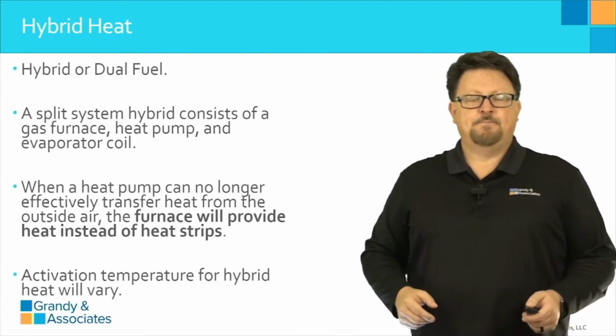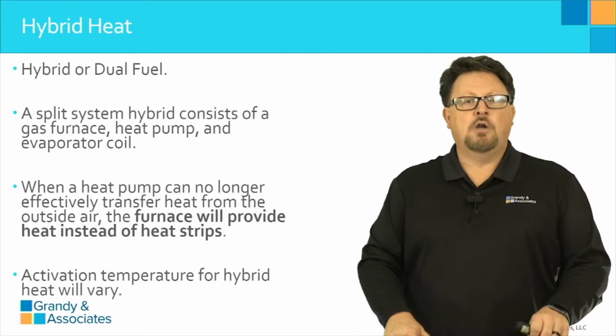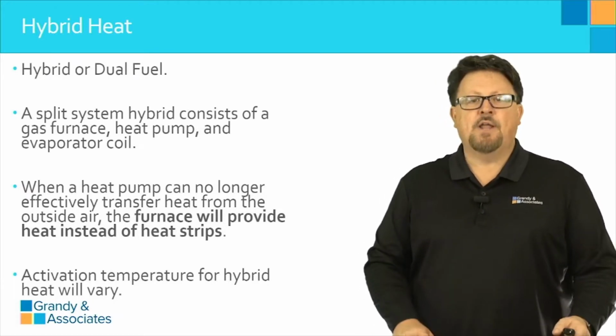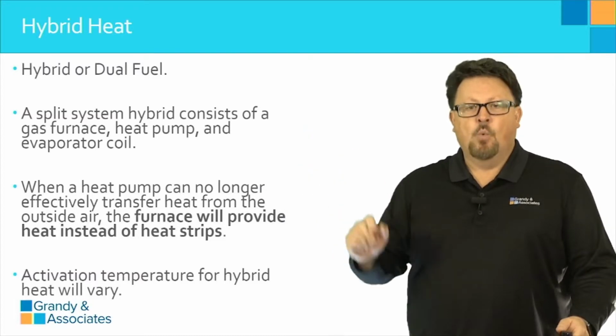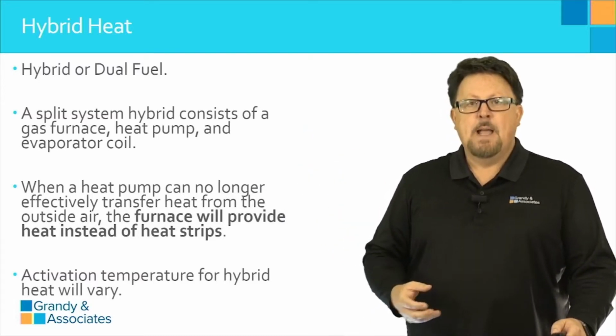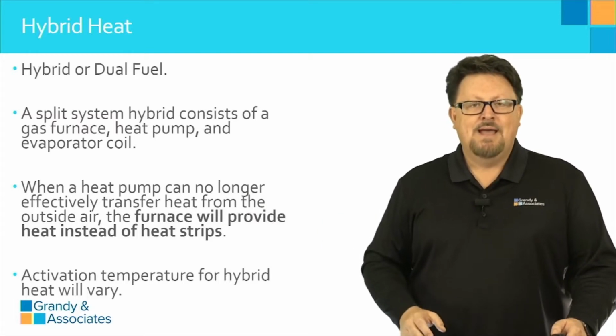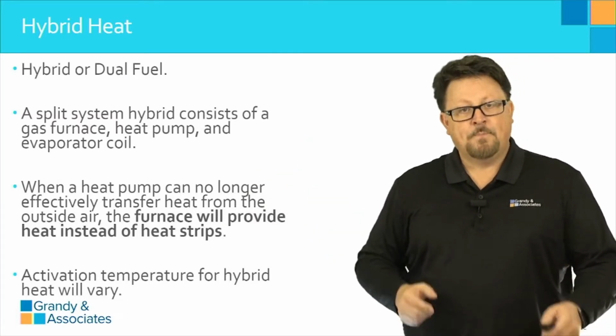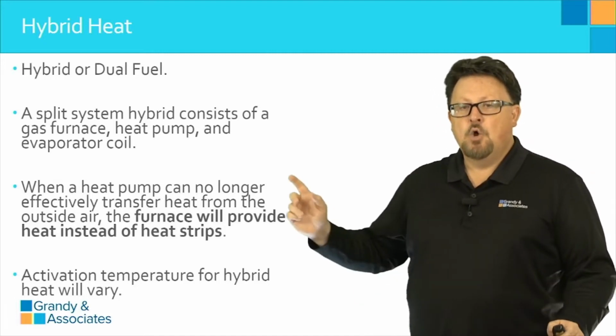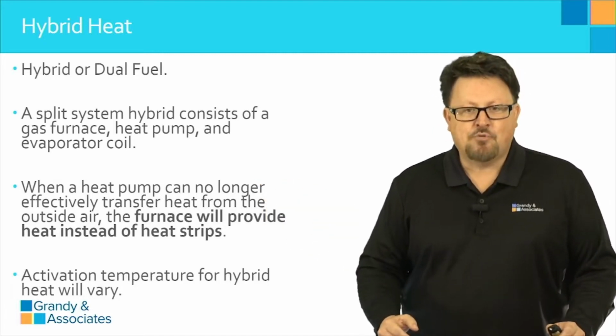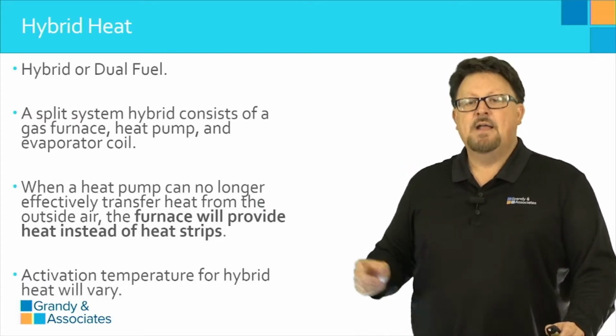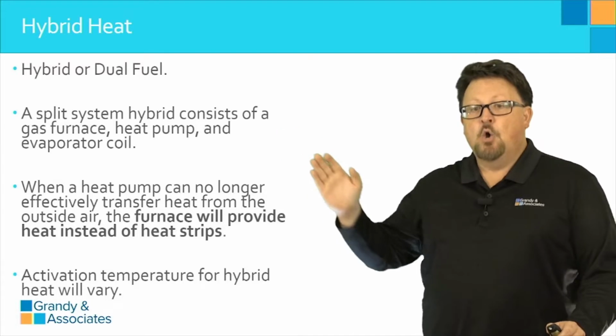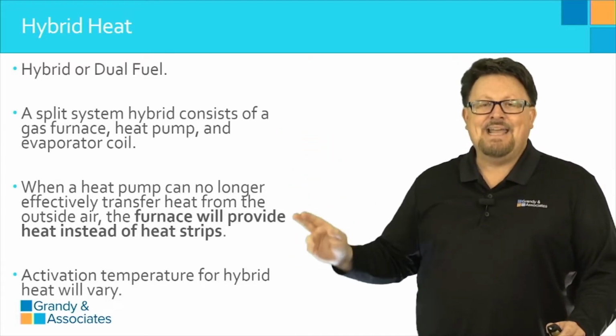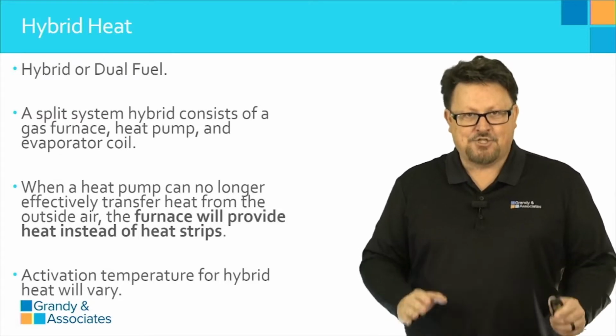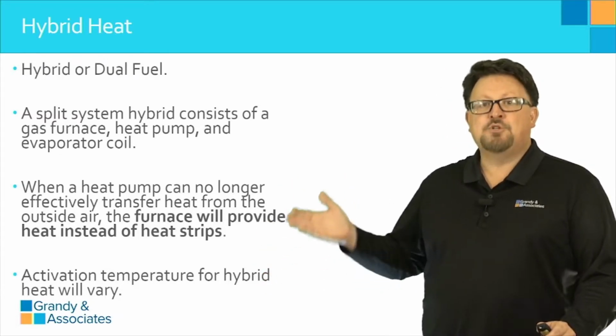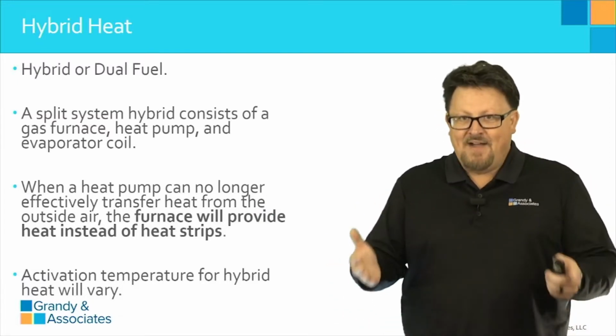There is an alternative, something called hybrid or dual fuel. In this scenario, a split system hybrid would consist of a gas furnace paired with an outdoor heat pump and an evaporator coil. The principle is still the same. When the heat pump can no longer effectively transfer heat from the outside air, the furnace, in this example, would provide that backup heat instead of the electric heat strips. Activation of the temperature of when that takes over, again, varies. A lot of factors go into that.